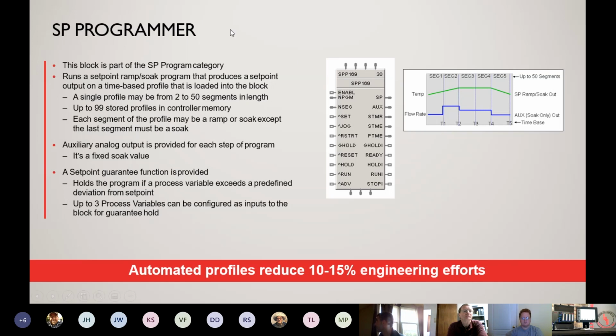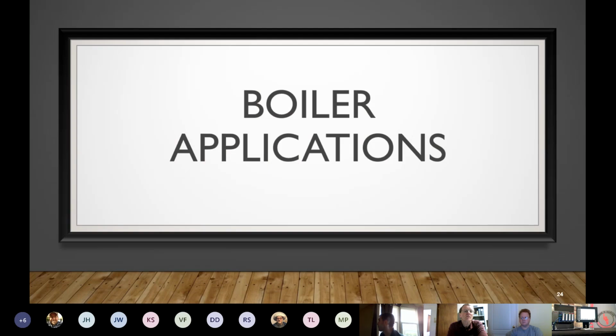This pretty much mimics the DCP programmer line that Honeywell has. So if you have an application with a DCP 250, DCP 100, or the obsolete DCP 550 from Honeywell, you can actually use the HC900 in place of those with the set point programmer to accomplish the same functionality as those other Honeywell programmers.